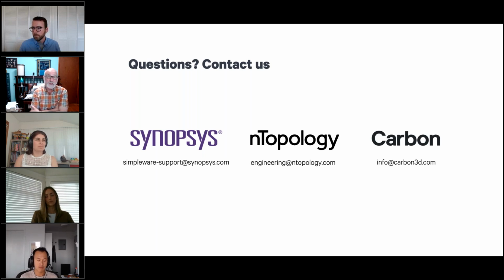In terms of certification, these materials don't get FDA clearance because they're not considered a medical device as such. The total product is. So the process flow would end up being developed by somebody wanting to work with the three entities simultaneously and create a certified process. The resins have been tested by certified laboratories, and we have those certifications on file. In fact, you can look on the website to see the ISO 10993 data clearances that we have for the resins.